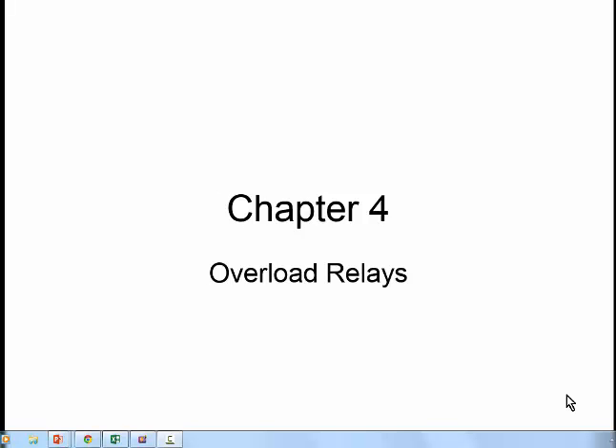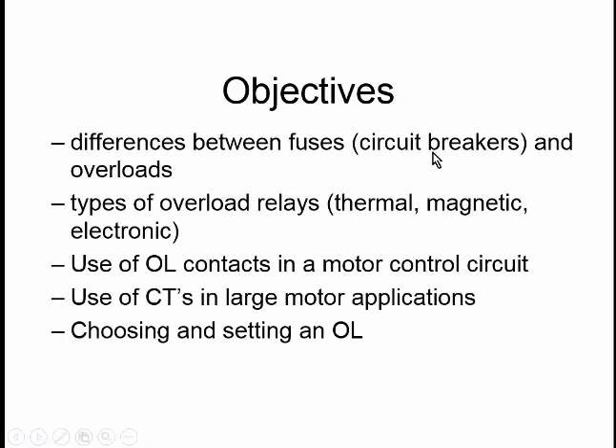Overload relays, these are an important part of your typical motor control system. They're being overcome by technology in that VFDs don't require them. Once you stick in an electronic motor controller, it can take care of the overload portion. But we're going to look at the differences between fuses, circuit breakers and overloads, some different types of overloads, how they're used in a motor control circuit, and we'll take a look at CTs and choosing and setting an overload.